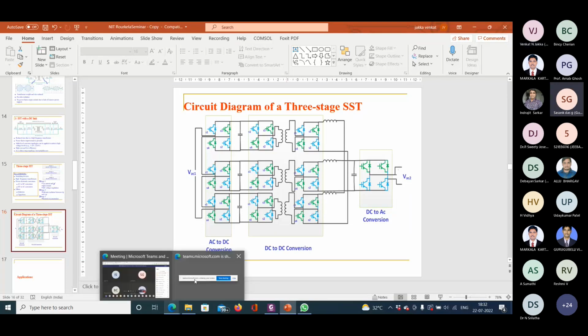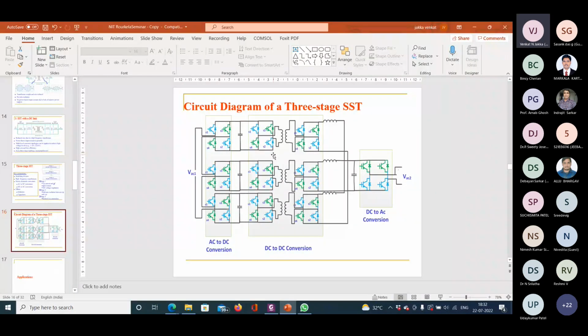Compared to conventional transformers, the size of these SST transformers is large. It is not true, because this figure looks bigger, but if you compare, say, a 10 kVA 50 hertz transformer and a 10 kVA 20 kilohertz or 50 kilohertz transformer, there will be a huge difference in weight and volume.